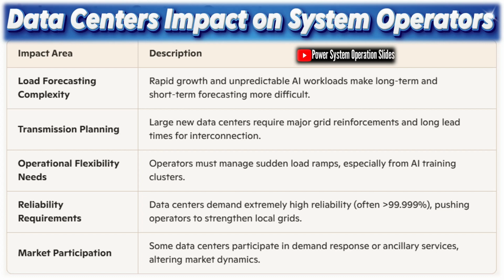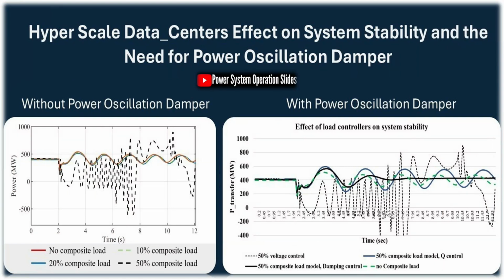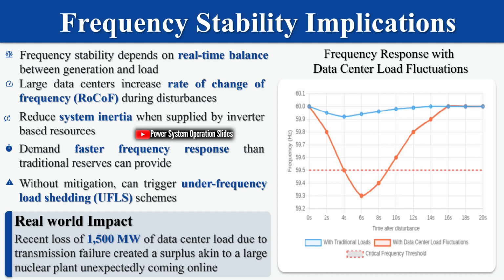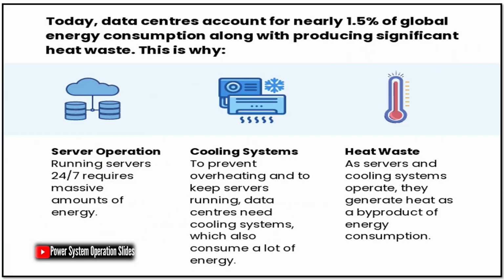Much of today's grid infrastructure was designed decades ago for predictable, slowly varying loads, unidirectional power flows, and limited power electronics penetration. Data centers challenge these assumptions by introducing high, continuous thermal loading, rapid power ramps, and potential bidirectional flows when on-site generation or storage is deployed. Grid reinforcement, new substations, transformers, and transmission lines typically require 3 to 10 years, while data centers can be built and energized in 12 to 24 months, creating a significant planning-execution mismatch for system operators.